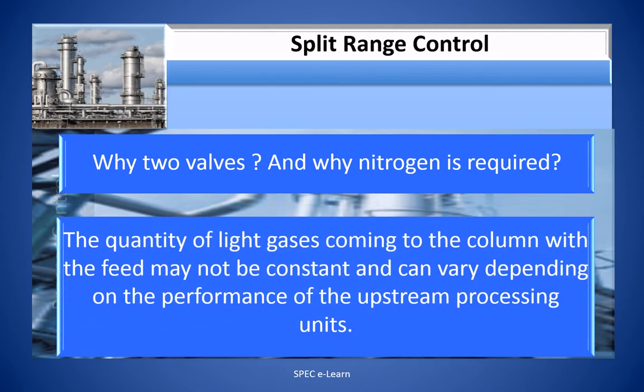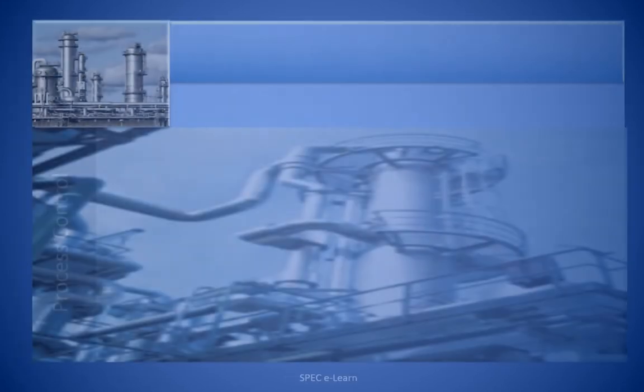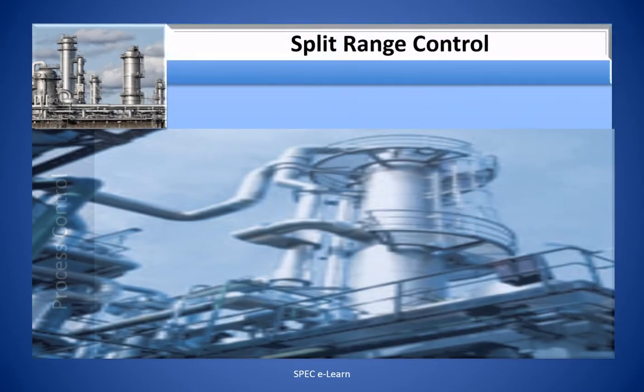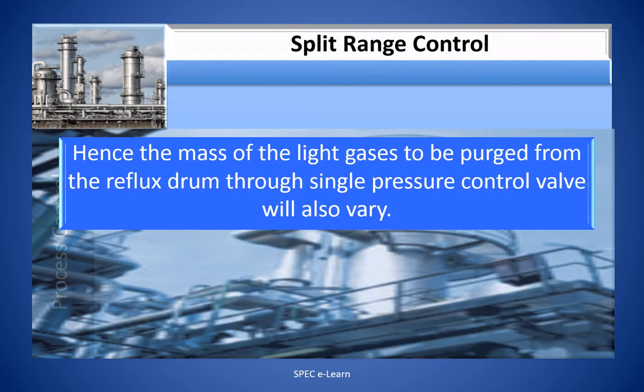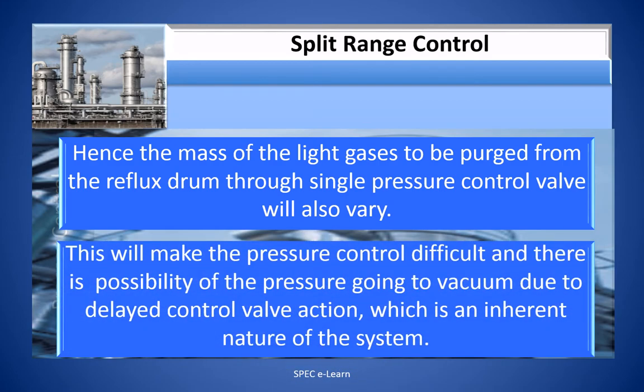The quantity of light gases coming into the column along with the feed may not be constant and can vary depending on the performance of the upstream processing units. Hence, the mass of the light gases to be purged from the reflux drum through a single pressure control valve will also vary. This makes pressure control difficult, with a possibility of pressure going into vacuum due to delayed control valve action.